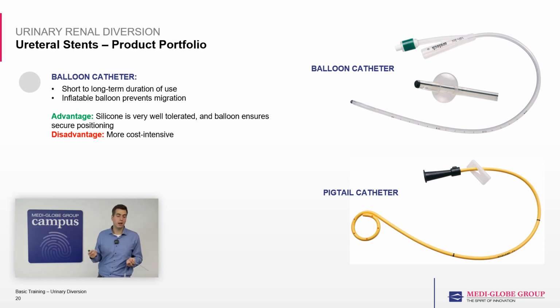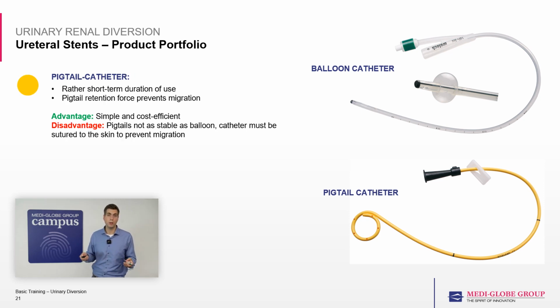Advantages for this kind of product is that silicone is a very high quality material. It's very well tolerated by the patient, and also the balloon is a very secure method to have the product in place during the indwelling time. On the other hand side, the disadvantage of balloon catheters is that they're quite costly in comparison to the pigtail catheters. The pigtail catheters you can also see on the right hand side of the slide, bottom right.